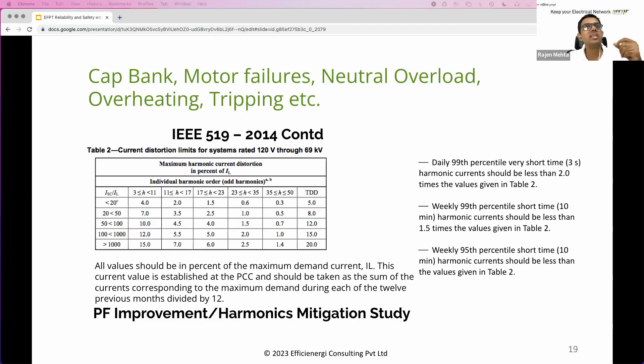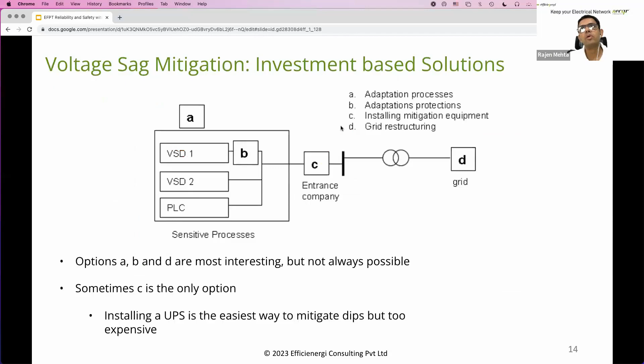But what kind of voltage event is it, based on the ones I shared in my presentation, the number of different events you find in a facility? It can be a dip, a transient, a sag, or a flicker, a rapid voltage change. Depending on that, the solution changes. If it's a transient, there's a different approach. If it's a voltage sag, a different approach. If it's a rapid voltage change, a different approach. More importantly, we'd like to understand what problem it's causing you because of that surge in the 33 kV panel, and why you're seeking a solution. We'd love to interact with you one-on-one.